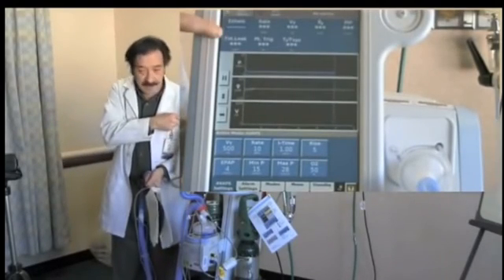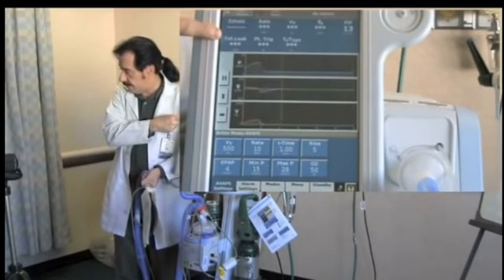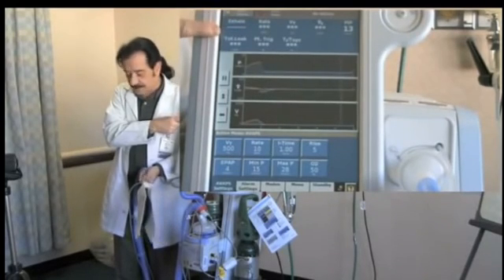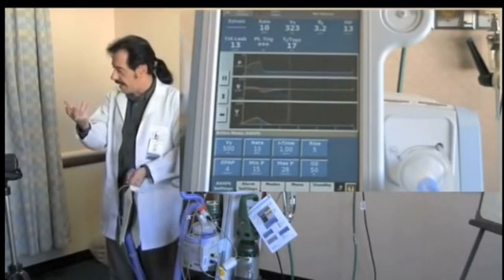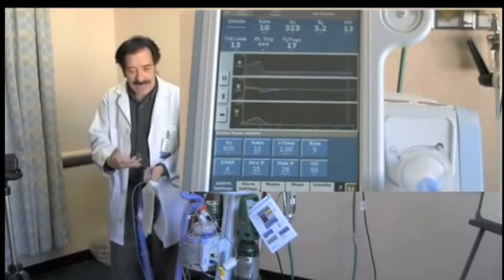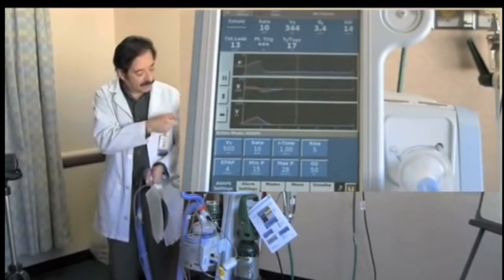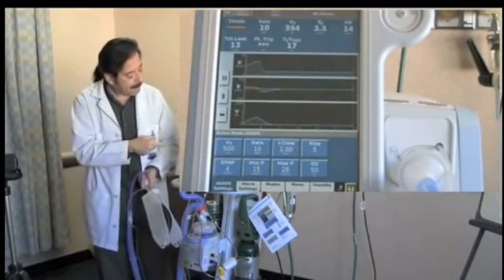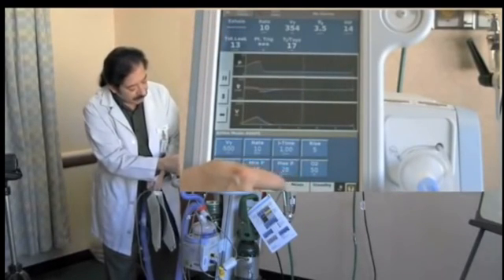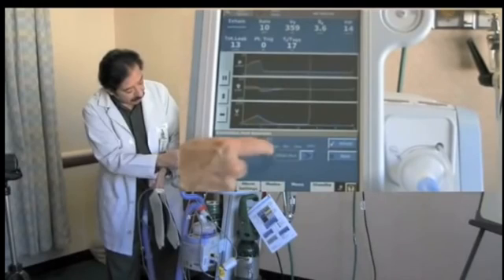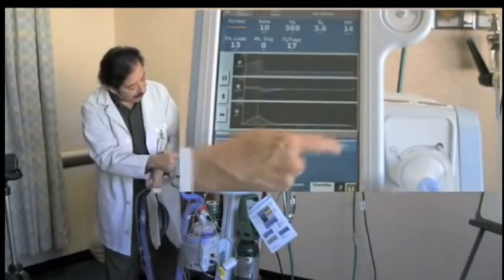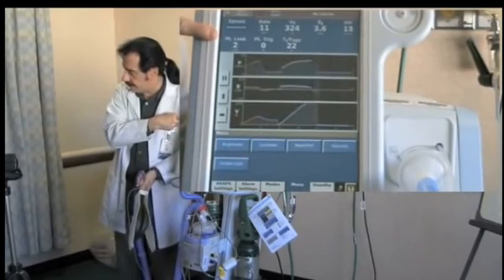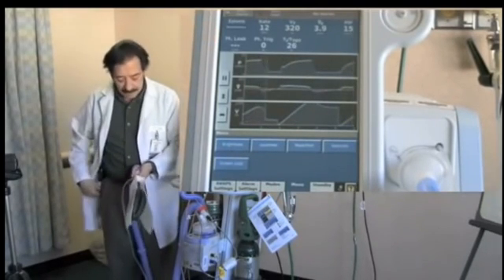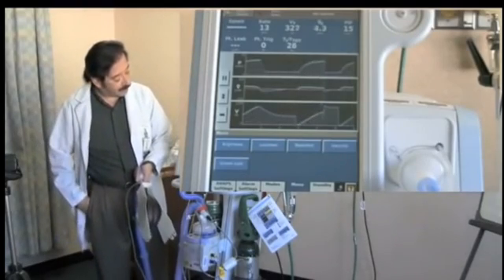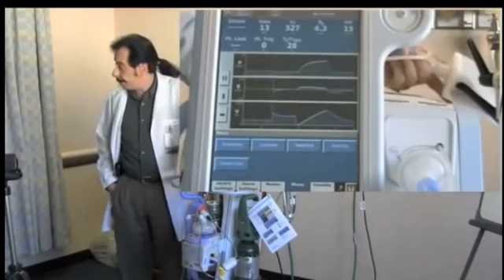But notice here that instead of saying patient leak, it says total leak. Okay? So it's not vouching. It knows that there's a leak there, but it doesn't know what's coming out of the exhalation port of the ResMed mask and what's coming out of the patient. So it's just going to report it as a total leak. Now in this situation, we'll say that I've got a patient with a trach. I'm using the disposable valve, and accept that. And now I go back from total leak back to patient leak, because it knows what's coming out of its Whisper valve. Okay. Any questions on that?